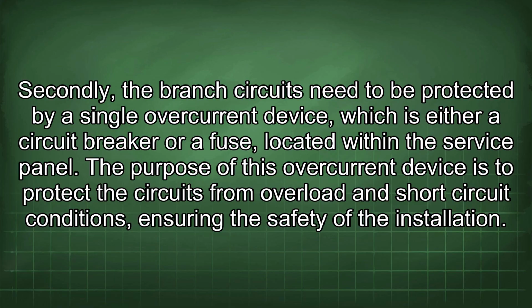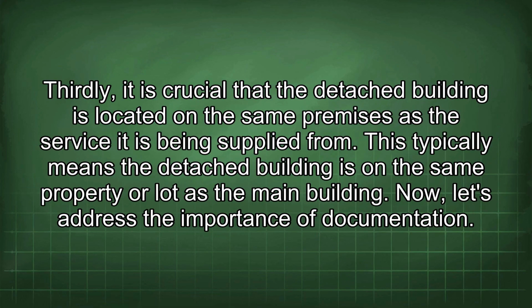The purpose of this overcurrent device is to protect the circuits from overload and short-circuit conditions, ensuring the safety of the installation. Thirdly, it is crucial that the detached building is located on the same premises as the service it is being supplied from. This typically means the detached building is on the same property or lot as the main building. Now, let's address the importance of documentation.